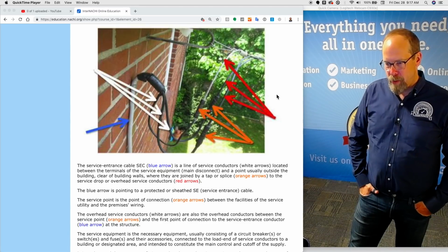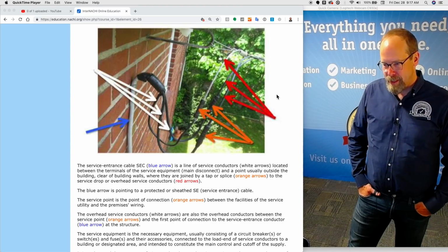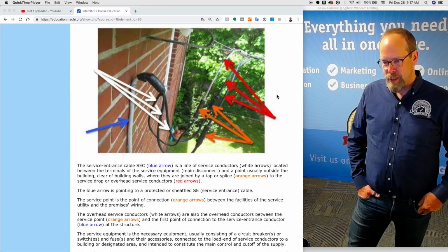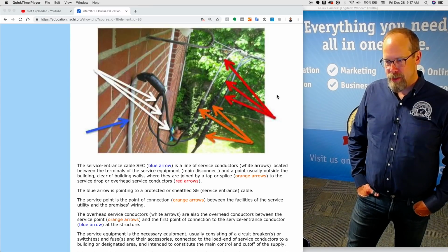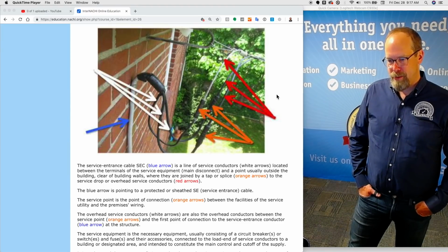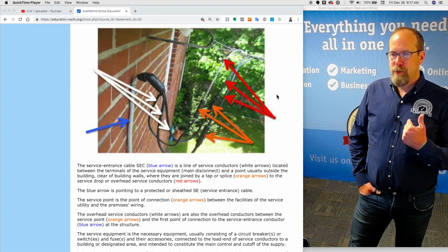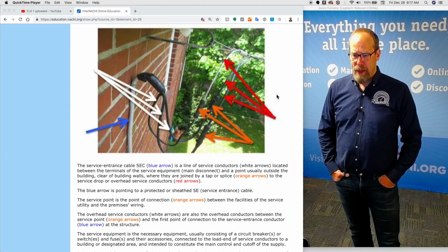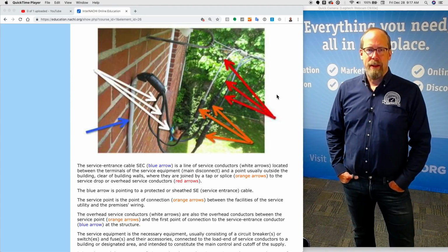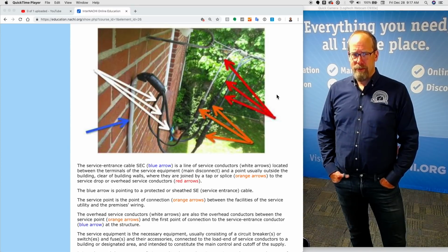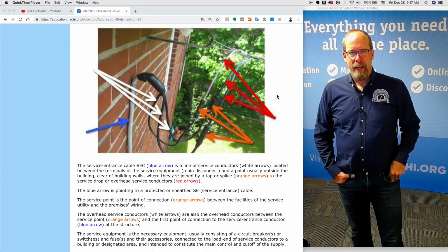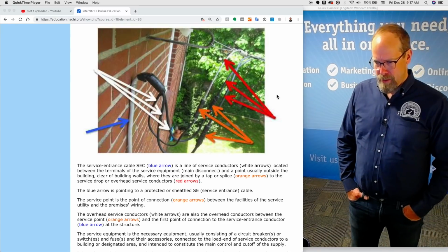Those white arrows are pointing to the conductors located between the terminals of the service equipment, which is the main disconnect, let's say, and a point usually outside the building where they're joined by a splice, the orange arrows, to the service drop or overhead conductors, and that's the red arrows. Now, the blue arrow is pointing to a protected or sheathed SE, service entrance cable. And there's where I pay particular attention. I want that cable attached well and in good shape. Sometimes very old SE cables have that cloth sheathing on it and it's deteriorated, and that would be a defect.